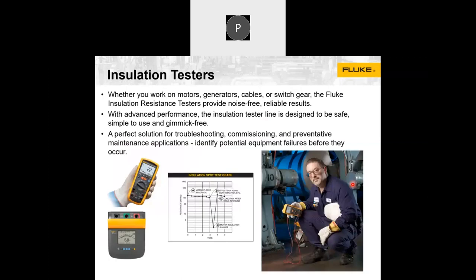Then comes insulation testing. As I said, failed insulation in the electrical system can create a lot of problems, even fire accidents. In communication systems it can create a kind of short circuit, which can spoil the devices or spoil the signaling itself, meaning it may not function the way it's supposed to. That's why you have to do insulation testing appropriately, as recommended by the standards, to ensure your facility runs appropriately.